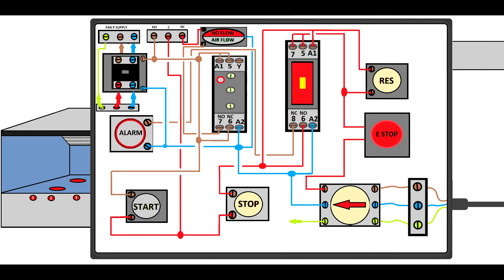You'll provide power through the stop button to the start button. The start has been activated just now, and the contactor which provides power to the fan on the left hand side top is activated. But you see in the middle you have a counter - that little dot flickering is a time delay relay which will override the differential pressure switches for 10 seconds. Once the fan reaches speed, then the differential pressure switches will override the time delay relay.